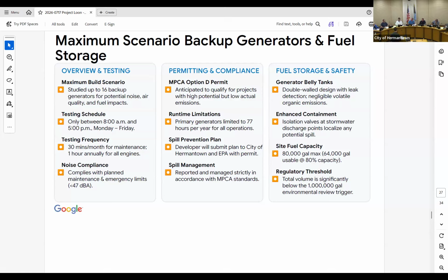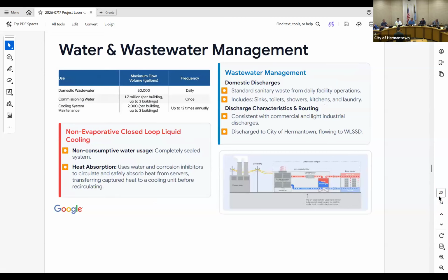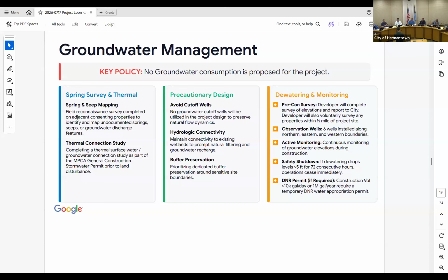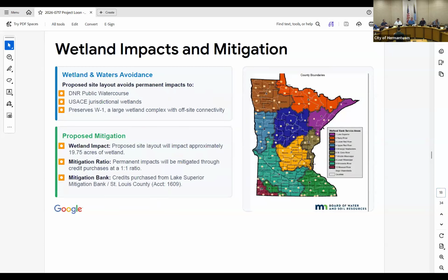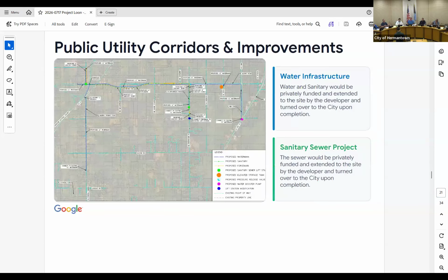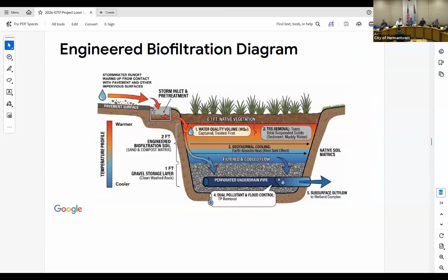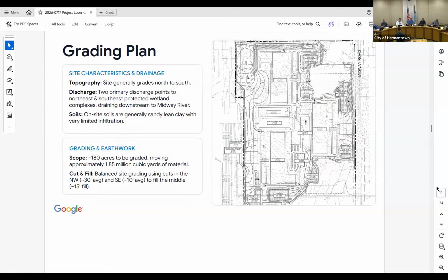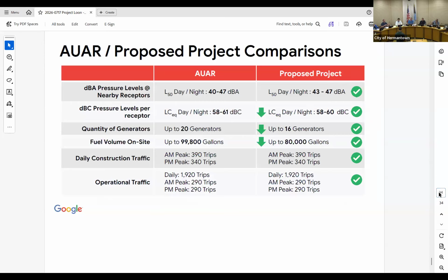Kevin: Most of my questions were answered, but we didn't really go high level into the chillers and cooling systems. My question is, it's a closed loop system, but you have to maintain it. Is there any point where the water put into the system needs treatment? Brian mentioned purging the system right off the bat. Can you give me some color on what's done to that water, like the antimicrobial additives? What else is added to the water, and at any point is water taken out of the system, and what happens to it? Also, if the system were to fail and a valve leaked, would the building be able to contain that?